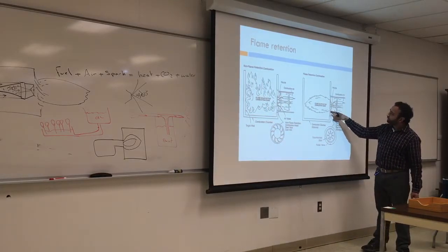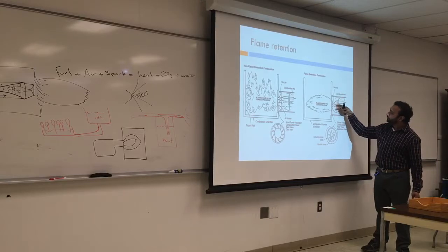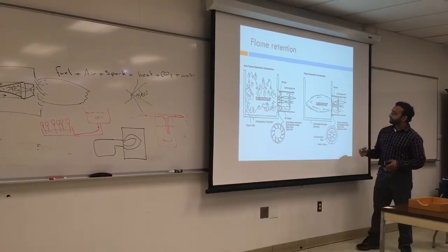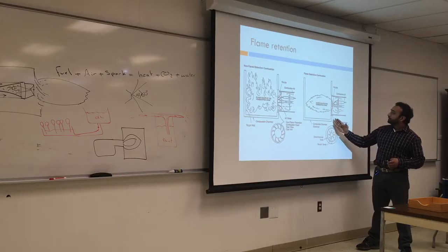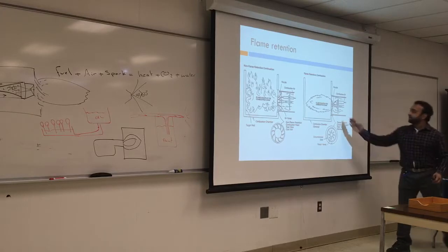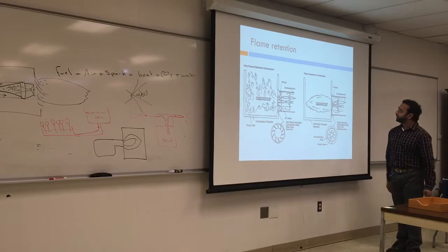And in this one you have the turbulator plate and the spray angle coming the right distance to the chamber. And the flame will be produced inside the chamber. It's not touching any of the walls. And that will make you think a little bit. What is the purpose of having the correct distance from the chamber and also the correct distance from the plate? We saw before when we adjusted the nozzle, the nozzle is too close to the electrodes. If they are too close to the turbulator, they will spark into the turbulator. So you want to be the right distance. So if you have no ignition, you probably want to check your clearances here and here and make sure they are the same distance from the plate. The correct distance from the plate, and the flame's going inside and not touching anything.